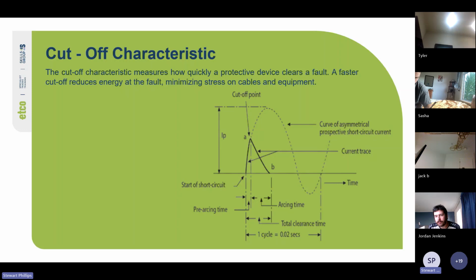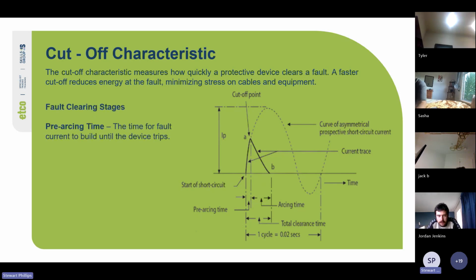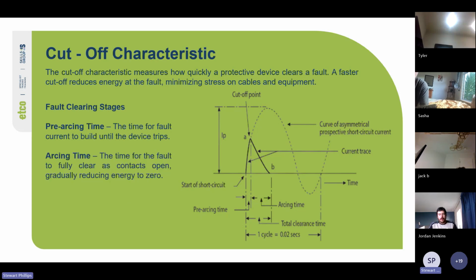Yeah, so then we've also got the curve of the asymmetrical prospective short circuit current, so that it's cut off before it can reach its total cutoff. Cool. So you've got fault clearing stages. You've got the pre-arcing time, the time for fault current to build up until the device trips. Then arcing time, the time for the fault to fully clear as the contacts open, gradually reducing energy to zero.